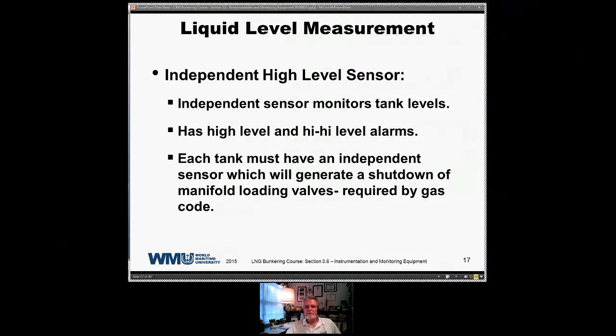As I said, you have two systems. You have one that monitors all of your tank levels, and this is the one where if the level gets too high, you're going to generate a high level alarm. If there's no response, you're going to get a shutdown of the fill valve into that one particular tank. But you also have what's called the high-high level alarm, totally independent. It's a physical point inside the tank. If liquid reaches that point, you're going to generate a shutdown where everything is shut down. That's going to close your manifold valves and everything, putting the system into a safe position. This is required by the IGC, the International Gas Carrier Code.